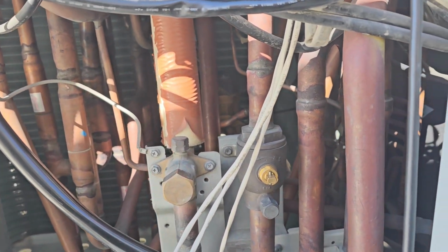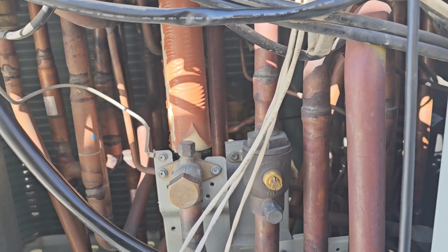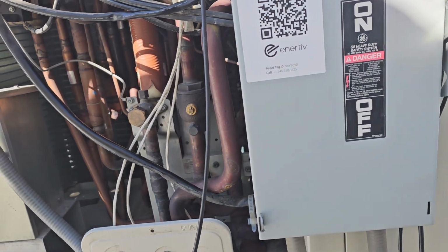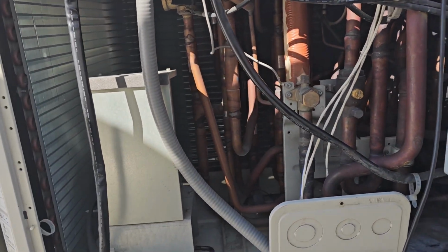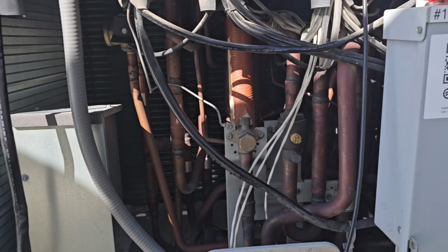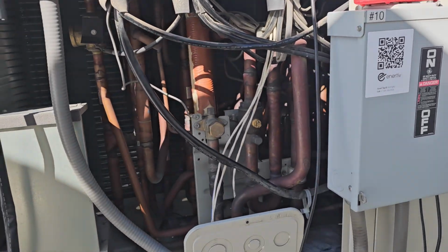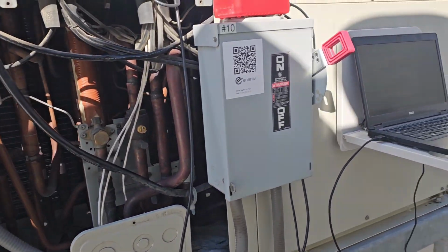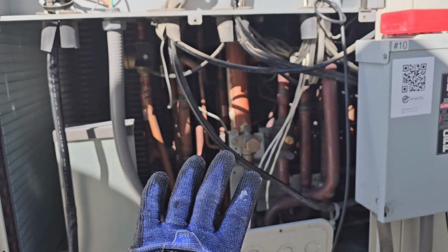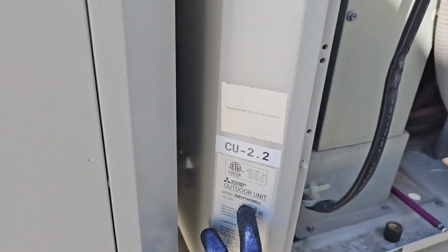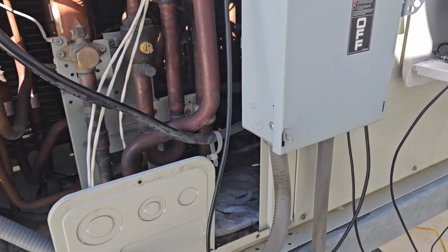I don't know why they were closed. I don't know why they were messing around with that, but all I know is it shouldn't have been. I also checked that one because if those ones are closed, well, I'm gonna double check that. But basically this whole floor, or not whole floor, but whole area was operating off minus this unit, but only that unit. So you're down 144,000 BTUs. So that's awesome.